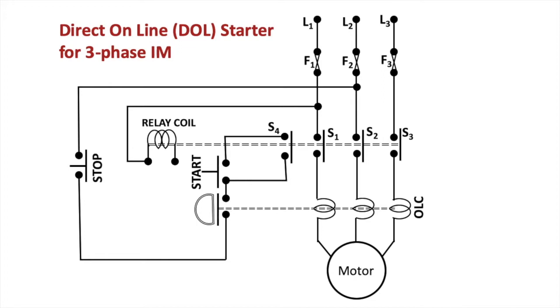Now first of all, we'll try to analyze why we need a starter for a three-phase induction motor, or why the different starting methodologies are employed. The motor at starting draws a very large current, normally 3 to 4 times its normal rated current. Because it's very large, it causes a drop in the supply system, as sudden extra current from the supply produces a voltage drop that can be observed as flickering. We don't want to affect the supply system because it increases the flickering in the remaining loads connected on the same supply system.